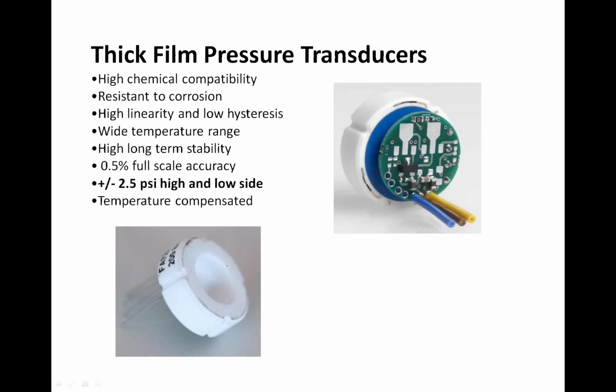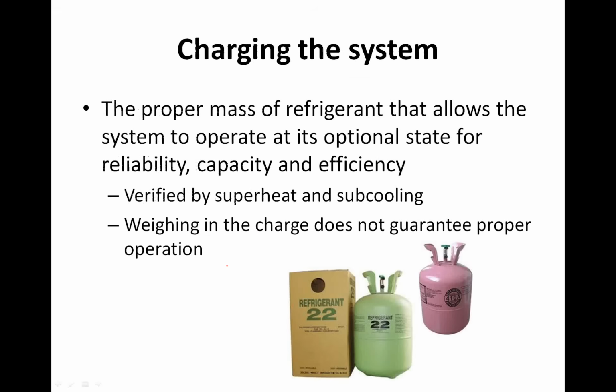Measurement technology-wise, we talked about this. This is a little picture of a transducer and what they look like. But unlike the mechanics of a gauge, where we actually got a Bourdon tube, which is a curved piece of copper and gearing and all that kind of stuff, we've gone to a solid-state pressure transducer, which is ceramic, which is highly resistant to corrosion, has very good linearity and low hysteresis, a very wide temperature range, and good long-term stability. So let's get into charging now, because we got to have the correct charge and some of the things that are going wrong with charge.